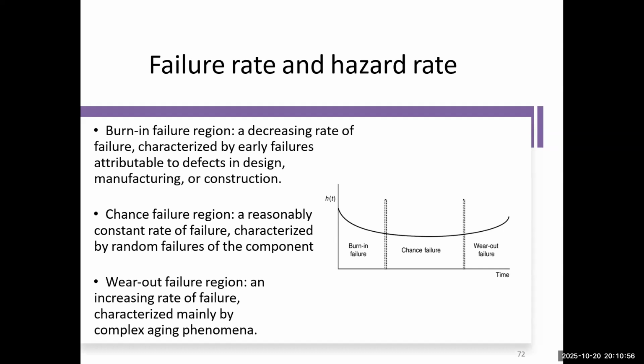Its hazard rate is very low and constant. A failure in this period might be caused by a random event like a foreign object entering the water. And after 15 to 20 years, the risk begins to climb again. The impeller corrodes and the motor insulation degrades, so the component is no longer as resilient as it once was. So that helps us to understand our failure rate and the hazard rate.